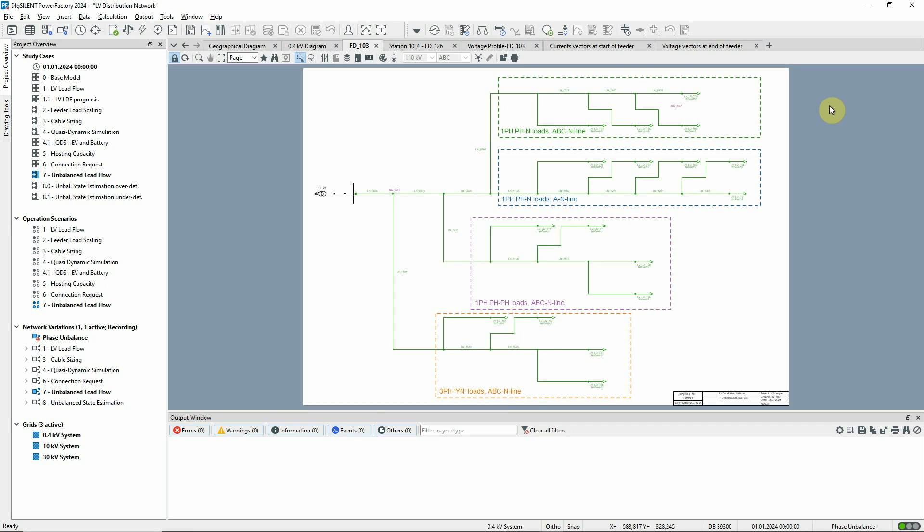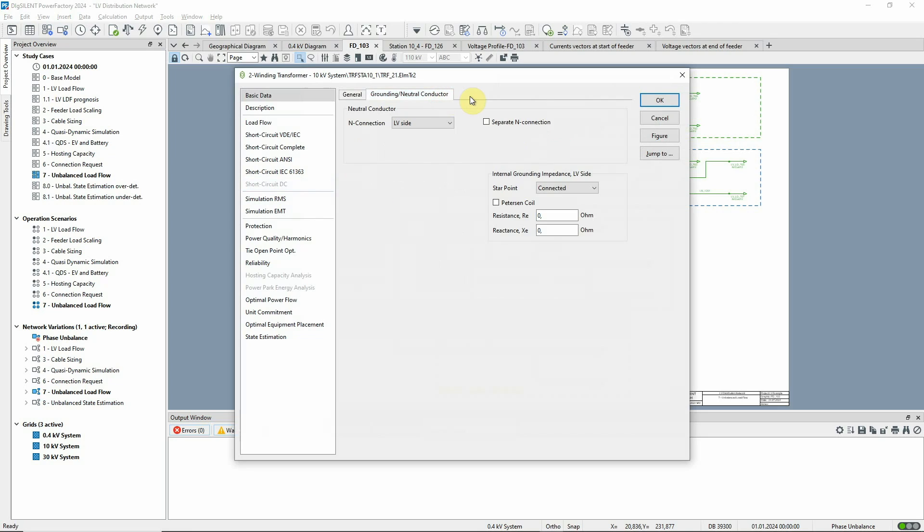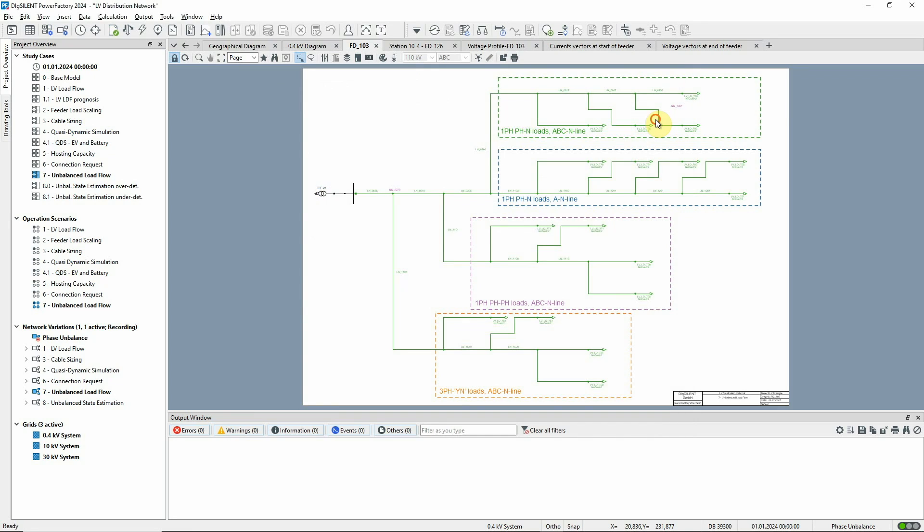Study Case Unbalanced Load Flow should be activated. In this diagram, the feeder FD103 is shown. If we open the transformer dialog and go to the Grounding Neutral Conductor tab, we can see that a neutral connection has been set. All the lines in this feeder have been modeled with a neutral conductor.